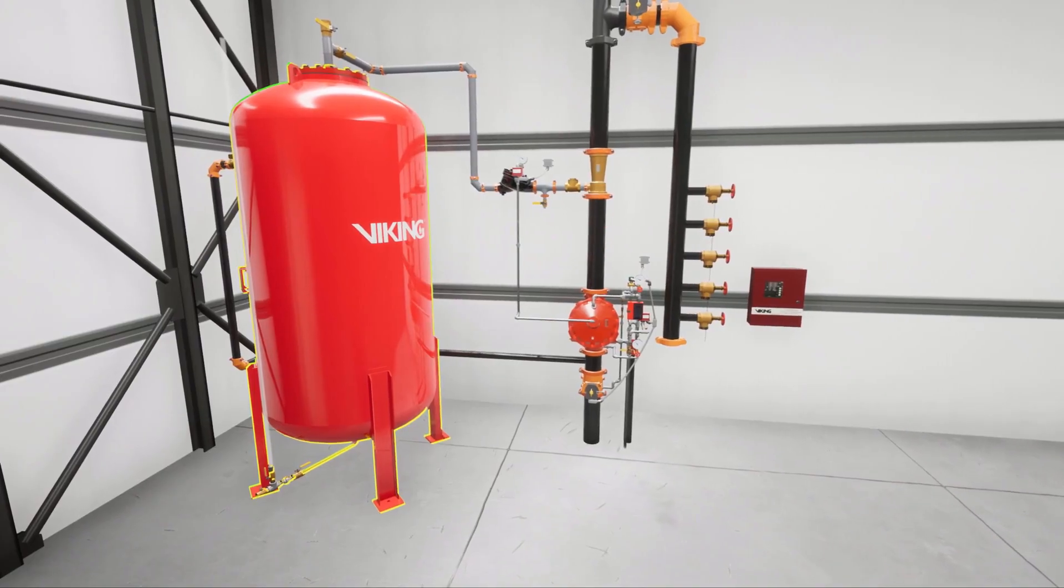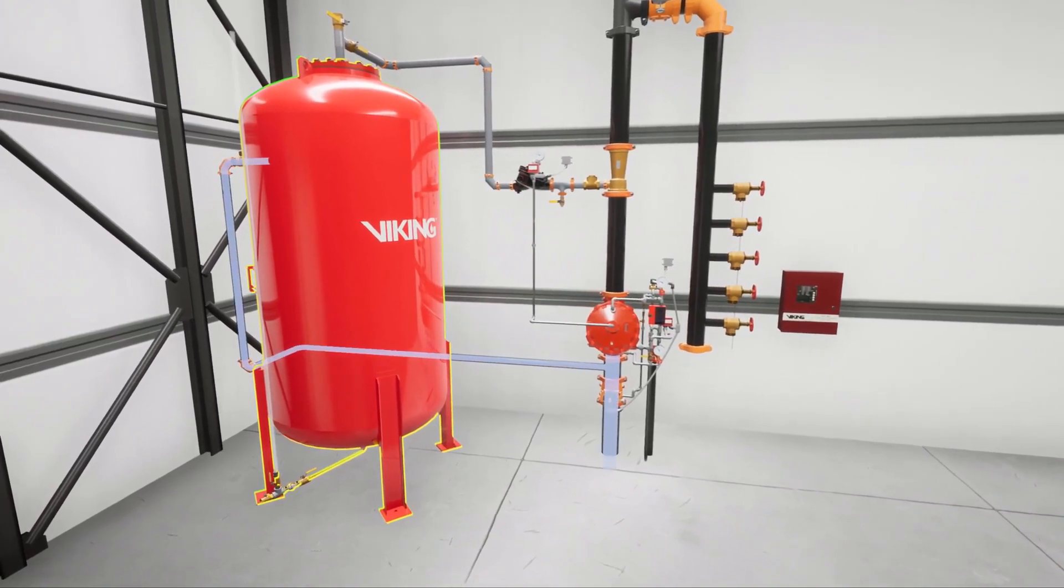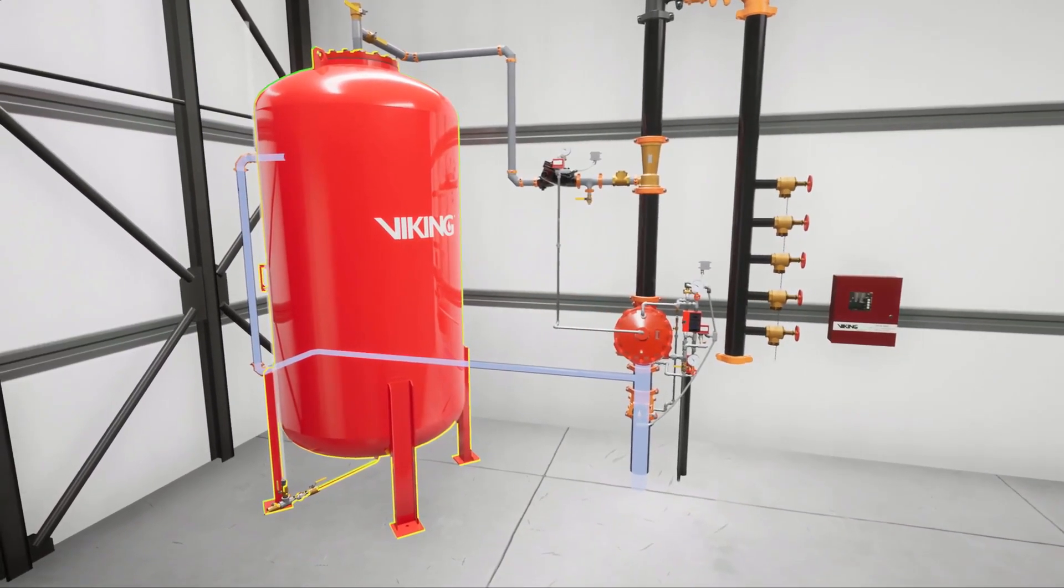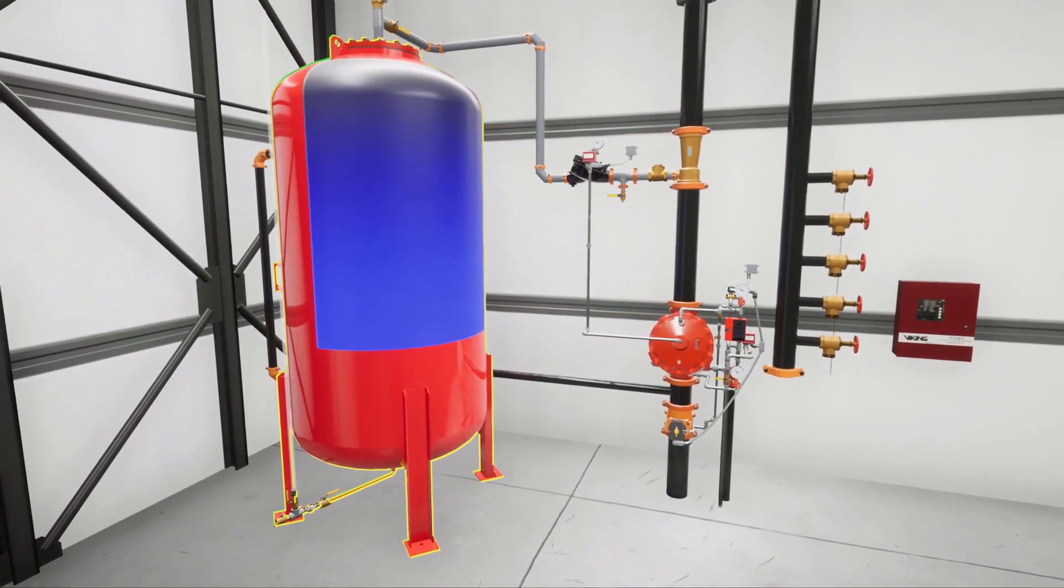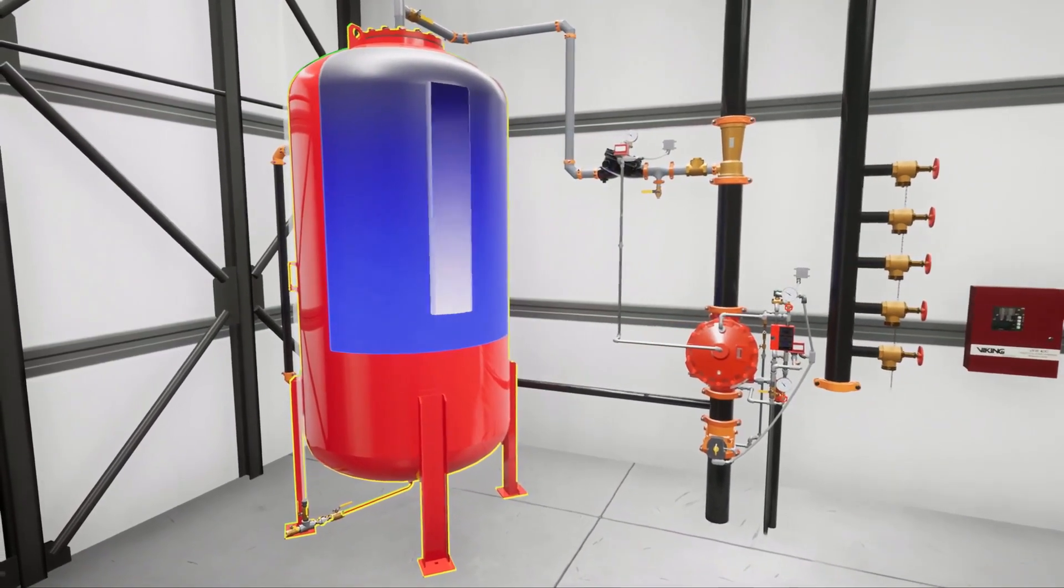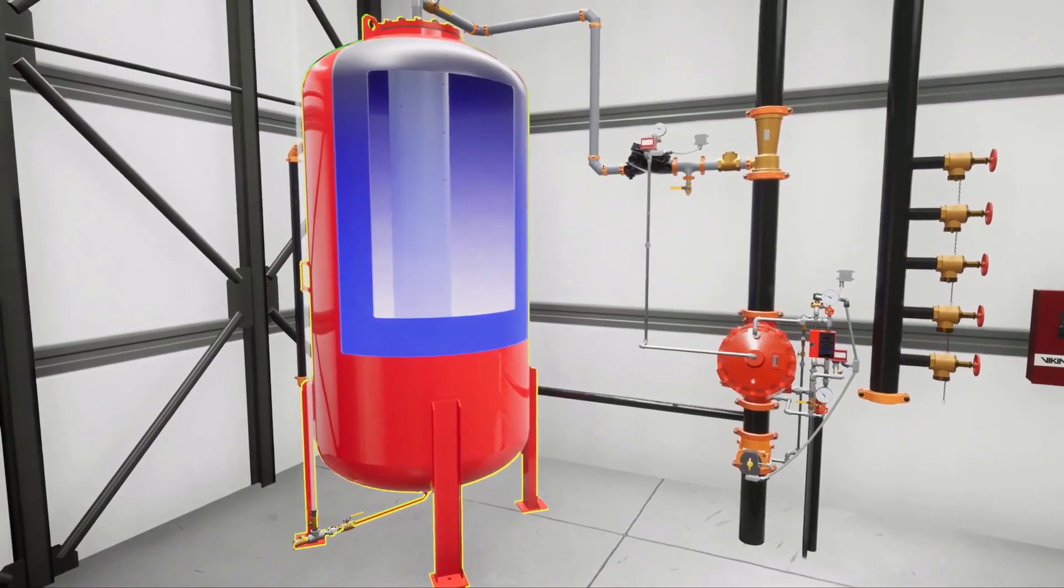A bladder tank is a device that is continually pressurized by the main water supply. The water sits between the steel shell and the rubber bladder. The bladder is filled with foam concentrate.